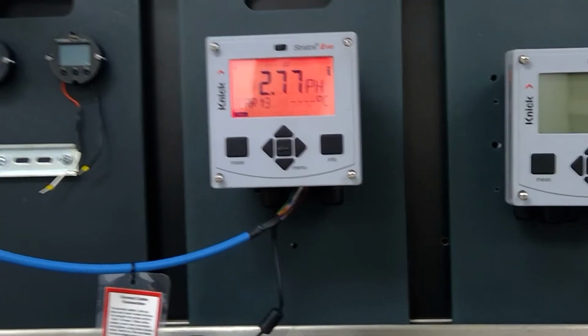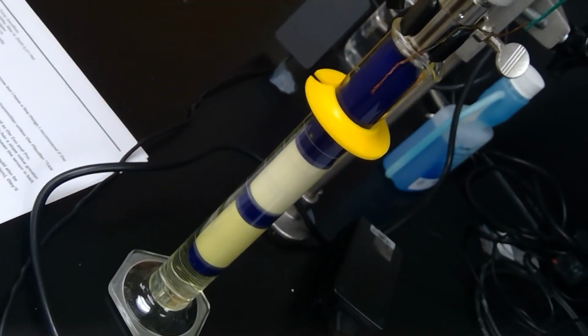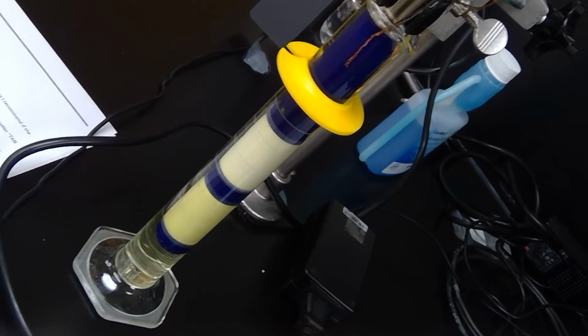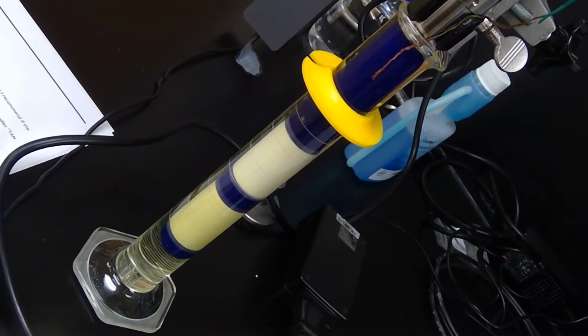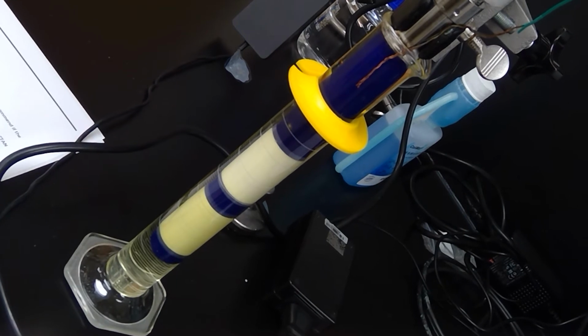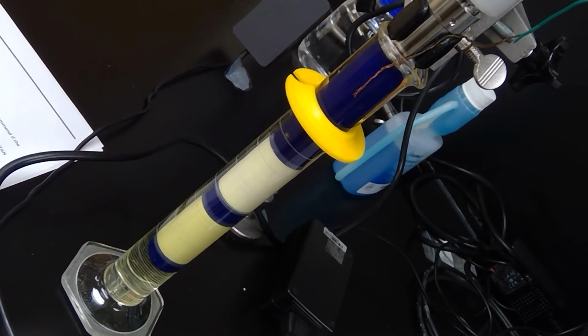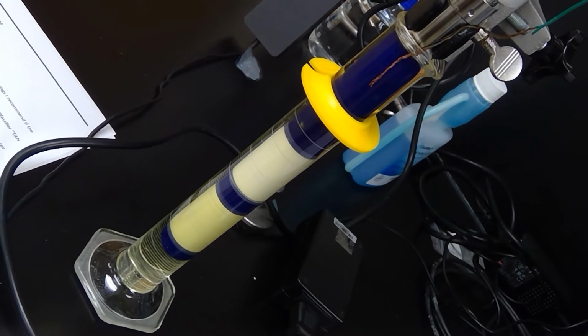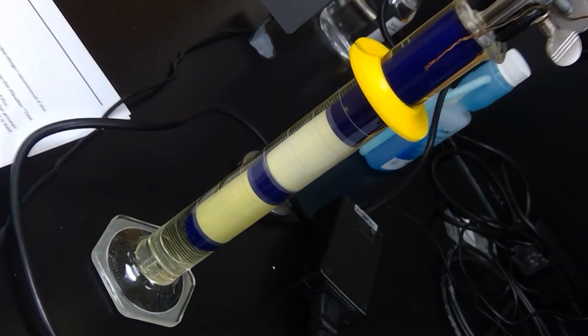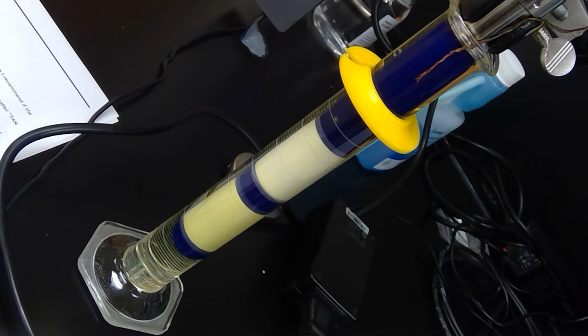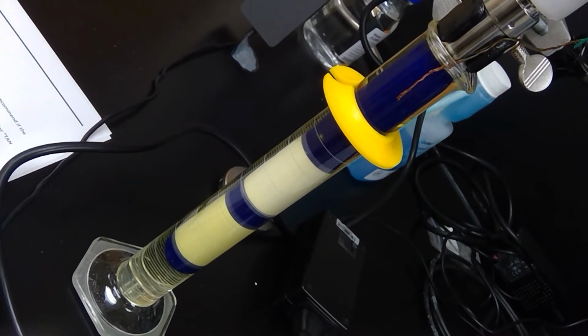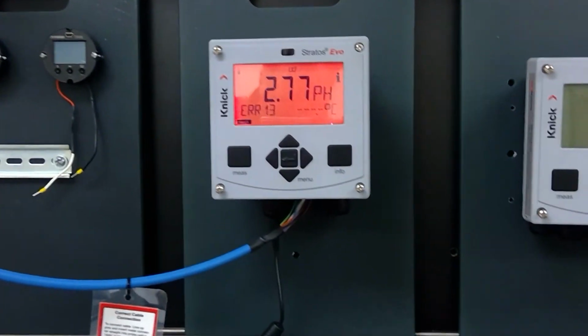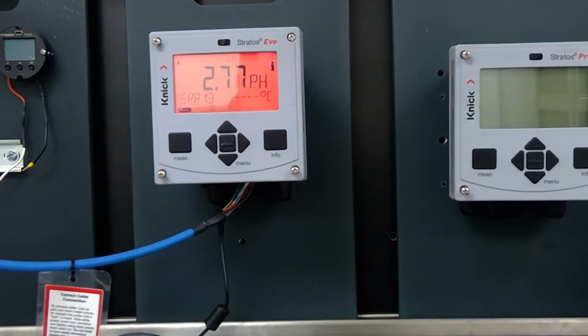The next thing that you'll want to do is, I'm going to move the camera here for a second, you're going to want to hydrate the electrode. In this case I have a beaker. You want to make sure that you have, in this case, a buffer 7 all the way above the ground electrode, which is that little dark dot. But more importantly, you want to have both of the bands submerged in the liquid. And you want to do that for 24 hours if you can. That ensures that when you go to actually do a calibration, you don't experience any drift out of the sensor.